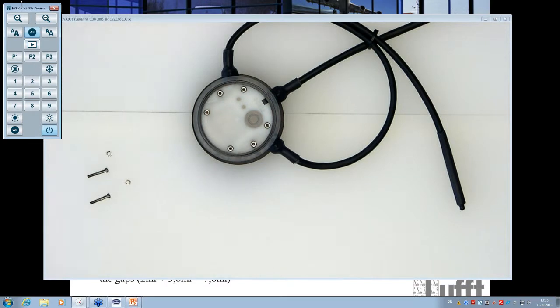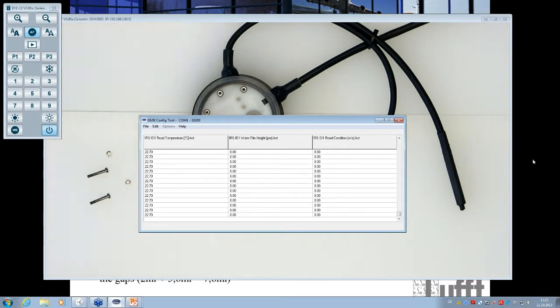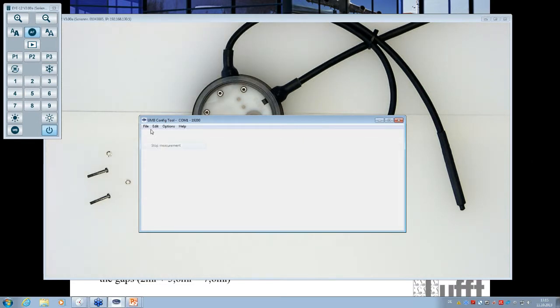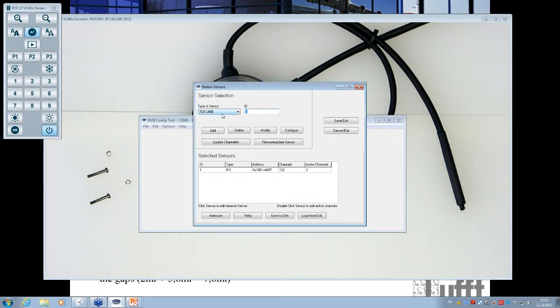Now, of course, what is needed to check the calibration or the values is the UMB config tool. So normally now you have to open your laptop, start the UMB config tool, and connect the laptop to the station. We will do that now. That means you go to Edit, Sensors, put the IRS into the selected sensor list, and activate the channels which you want to see. Normally in this case, because we want to check the water film, you activate a water film channel. After that, you go to Save and Exit.